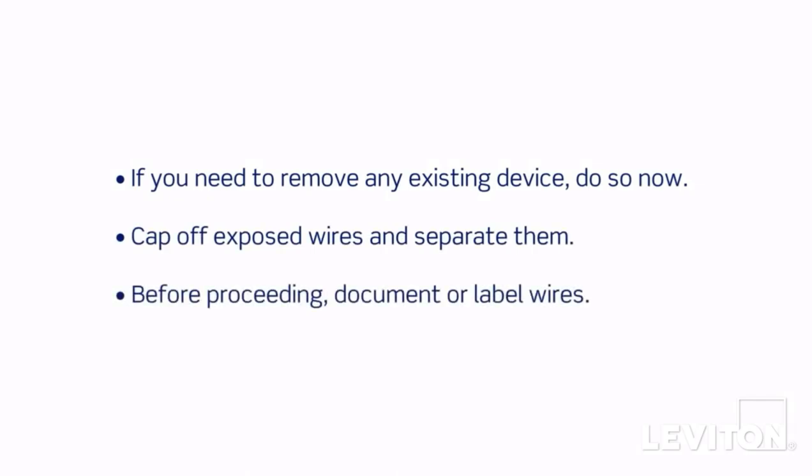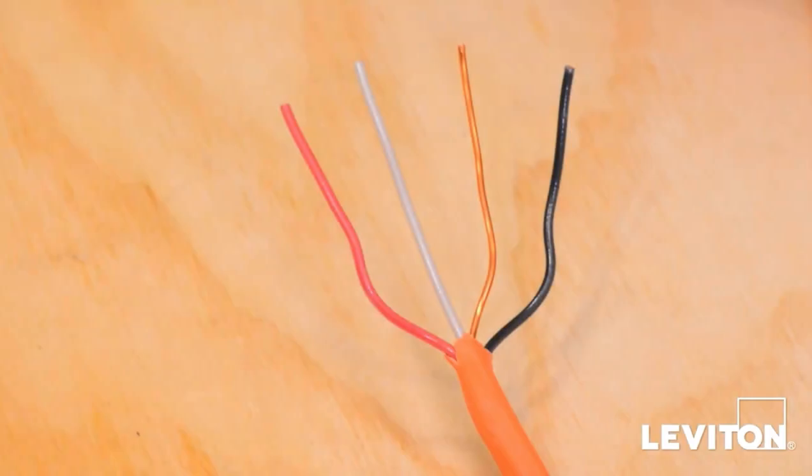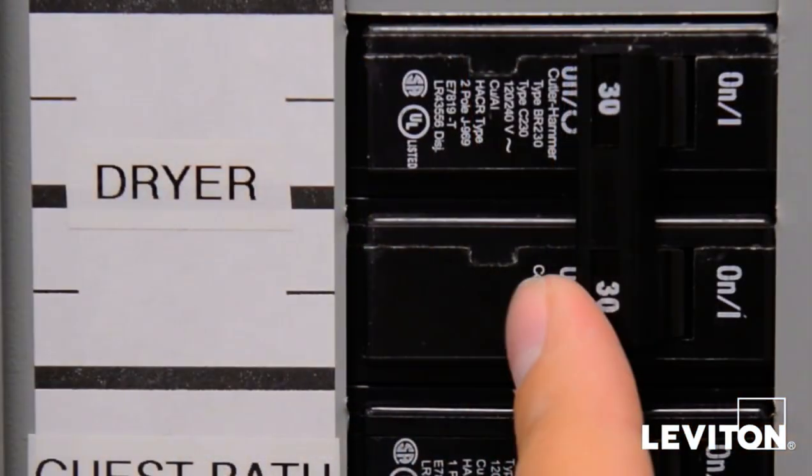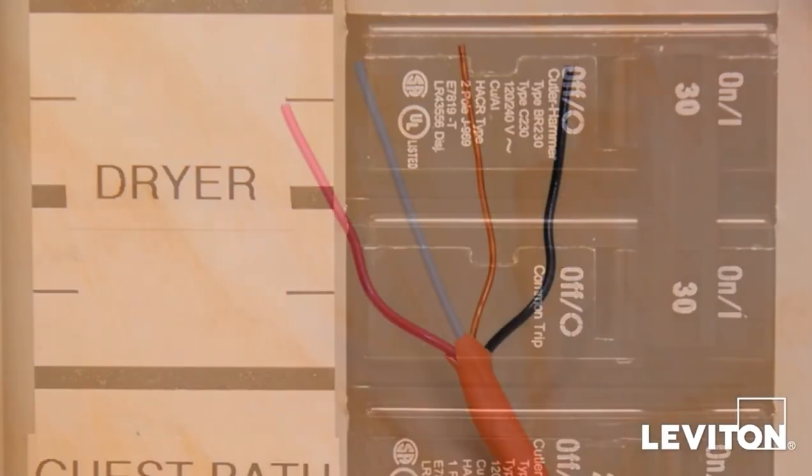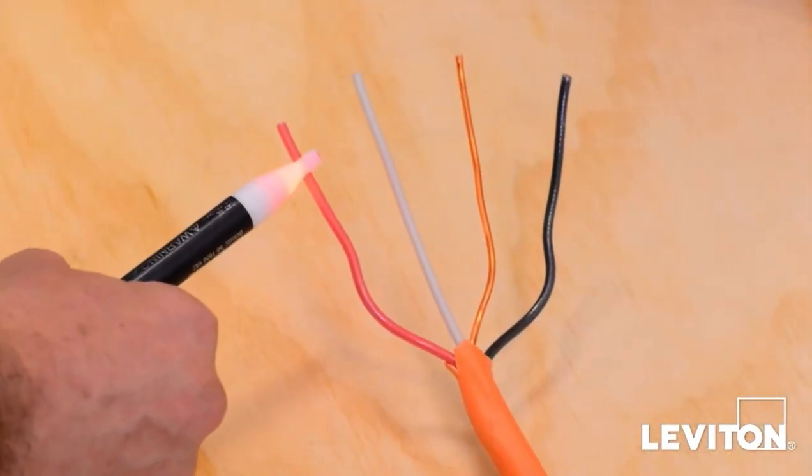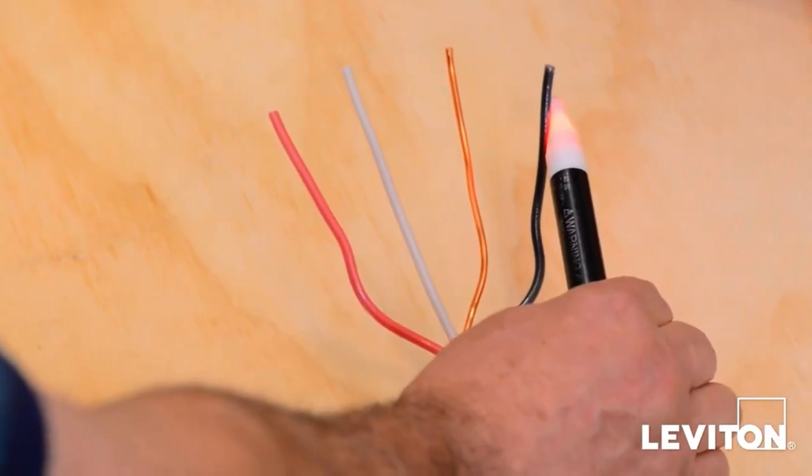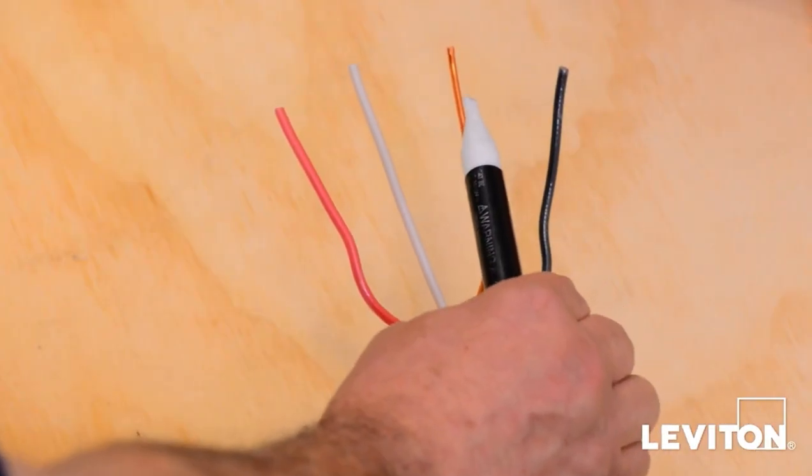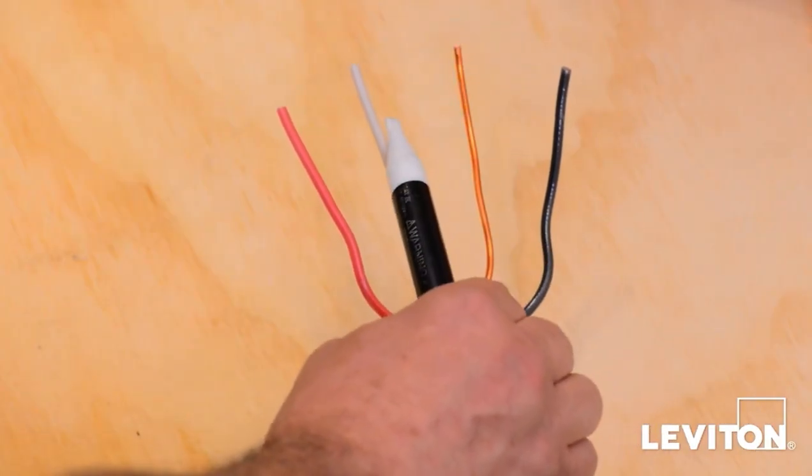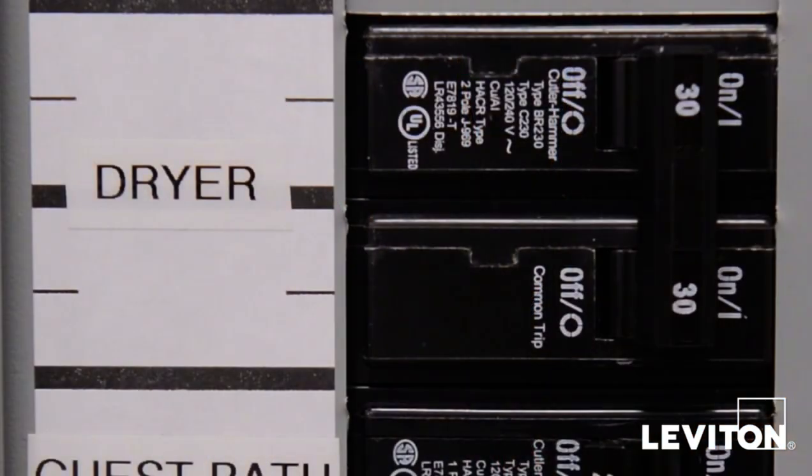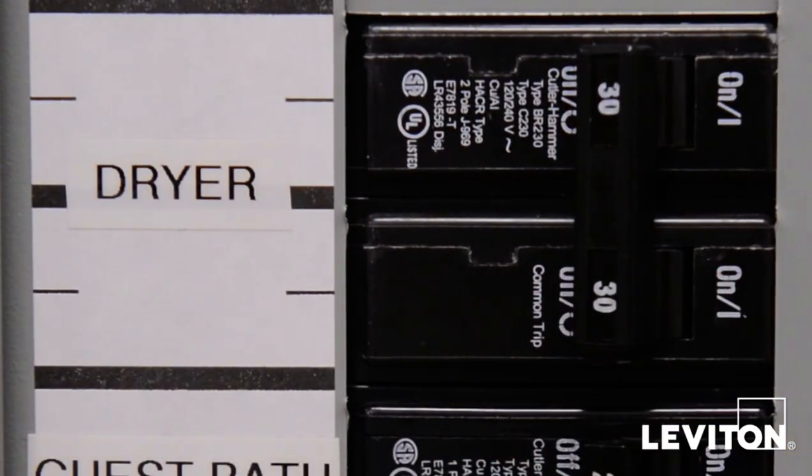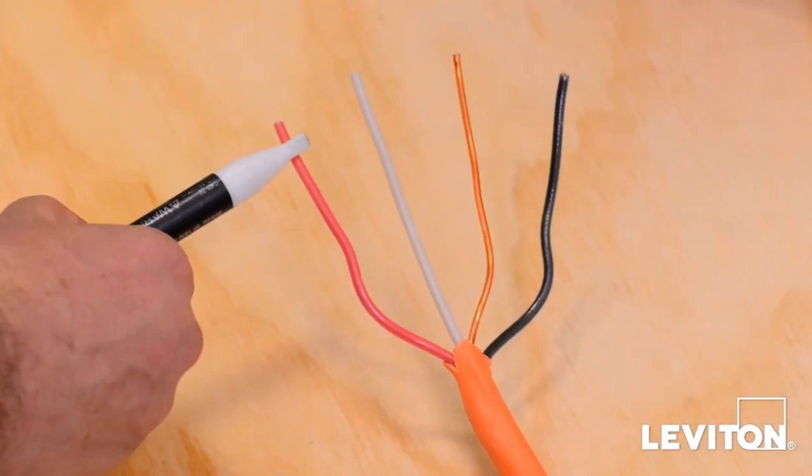Before proceeding, be sure to document or label wires for future reference. Now we need to identify the two hot wires. To do this, turn the circuit breaker back on. Carefully use the voltage tester to test each wire. The hot wires will be indicated by the tester. Once identified, turn off the circuit breaker to shut power and test to ensure the power is off.